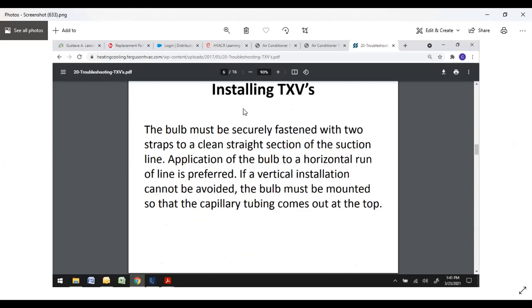Now mounting, these are important. Rheem actually gives you a nice mounting clip. They set it up for you to mount the bulb outside the coil, so it's easy to access, easy to mount. The bulb must be securely fastened, if it comes with two straps, or Rheem has the one solid strap, to a clean, straight section of line. Don't mount that on a joint because you will not have proper bulb transfer. Ideally you want a horizontal run. If not, you can do vertical, but the bulb must be mounted so the capillary tube comes out the top.